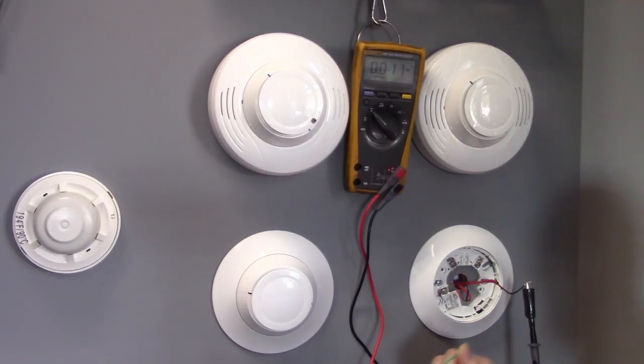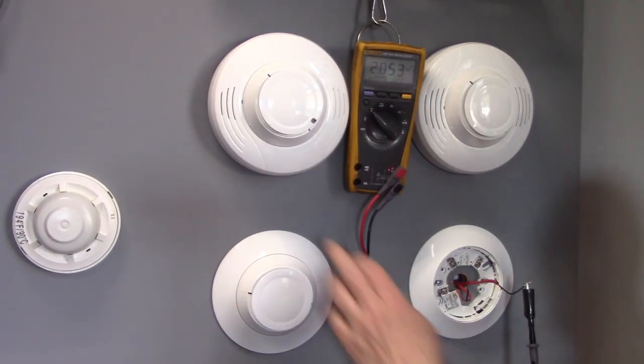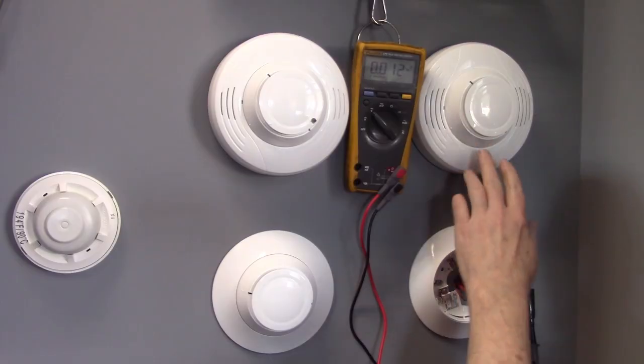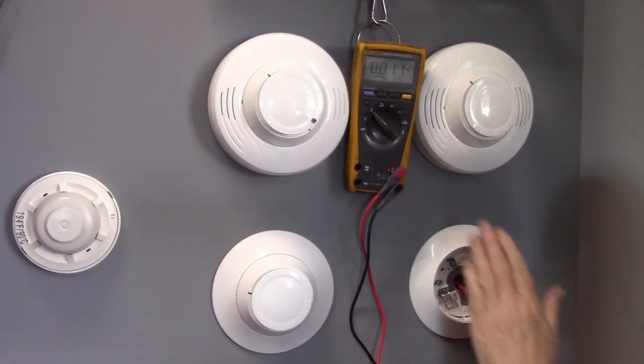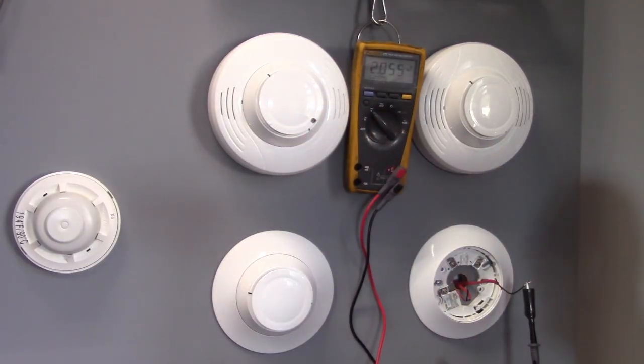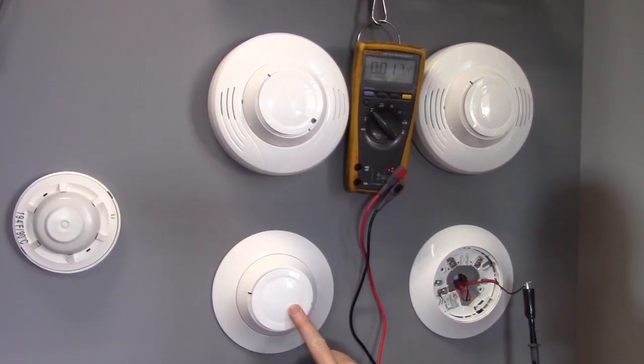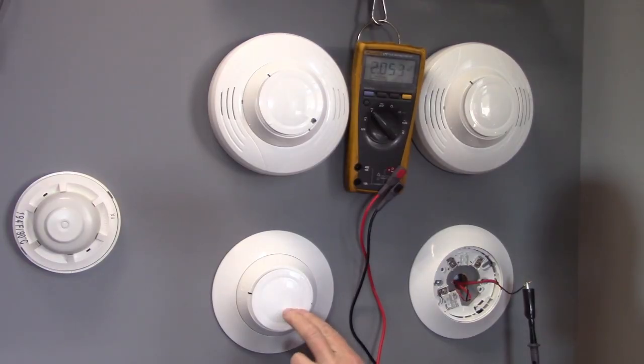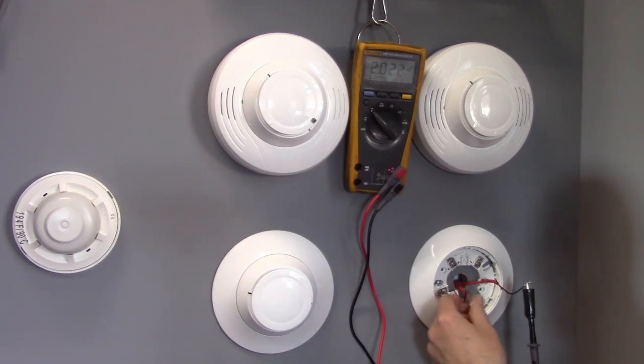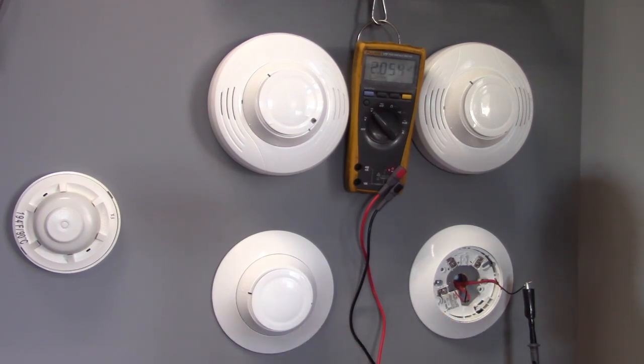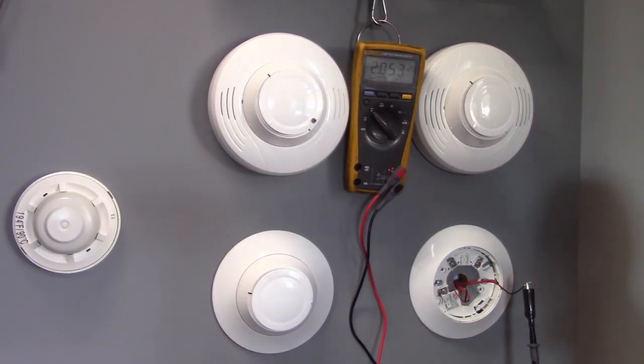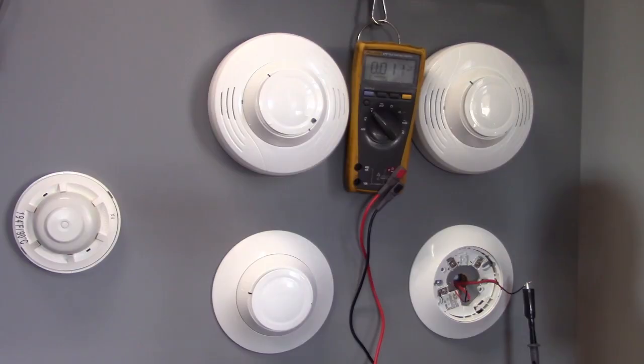You can do a little walk around. These detectors are still blinking, so they have power. So that means they're towards the panel. This detector is no longer blinking. So that means it's further from the panel. So it's on these wires. So I would move to another detector in that direction. And you just repeat this process over and over again until you can narrow it down between a couple of devices.